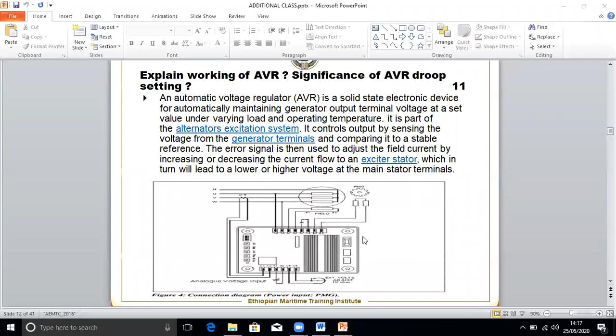The automatic voltage regulator is a solid state electronic device for automatically maintaining generator output voltage at the set voltage under varying load and operating temperature. It is a part of the generator excitation system. It controls the output by sensing the voltage from the generator terminals and comparing it to a stable reference. The error signal is used to adjust the field current. Basically, what the AVR is doing is varying the field current, by increasing or decreasing the current flow to the stator exciter, which will lead to lower or higher voltage at the main stator terminals.